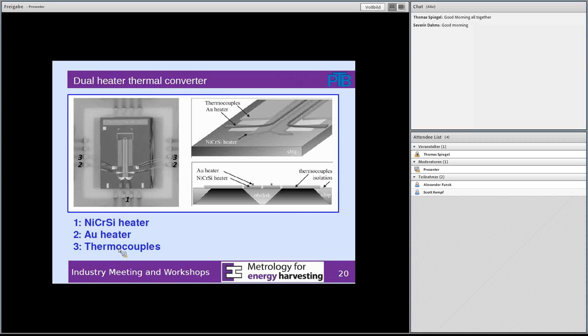Another thing is that the substrate is silicon, and it's not pure silicon, it's doped silicon, so it has a finite conductivity. It's not an ideal isolator. And so you get losses also at higher frequencies due to capacitively driven currents in the substrate. The remedy is to put all this on another substrate. We have thermal converters on quartz. This can be used up to at least 300 megahertz. We have not fully tested this, but it works. So this would be one idea.